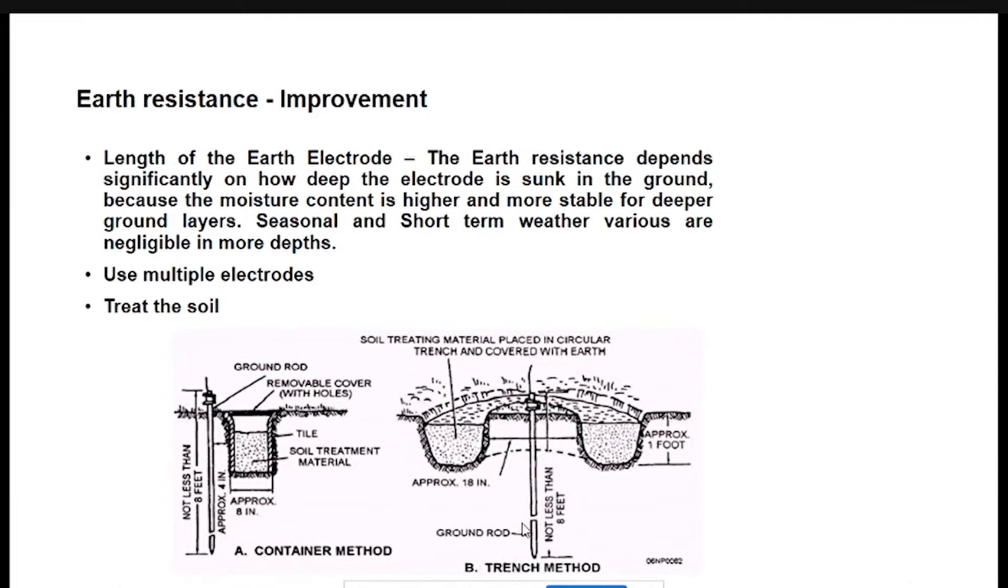Salt and charcoal should not be provided along with the electrode because the electrolyte of the salt and charcoal is sufficient for the electrode to activate. If you put the salt and charcoal directly to the electrode, it will eat away the electrode, so the efficiency of the earth resistance will be totally affected.